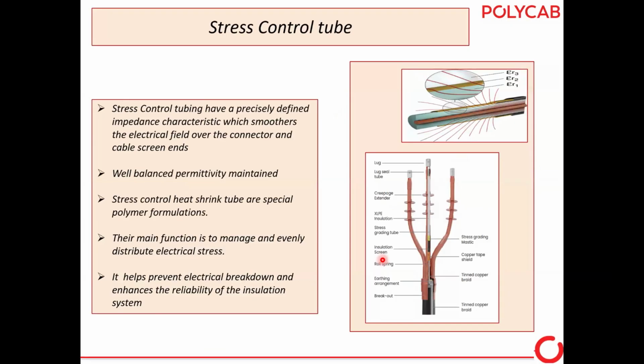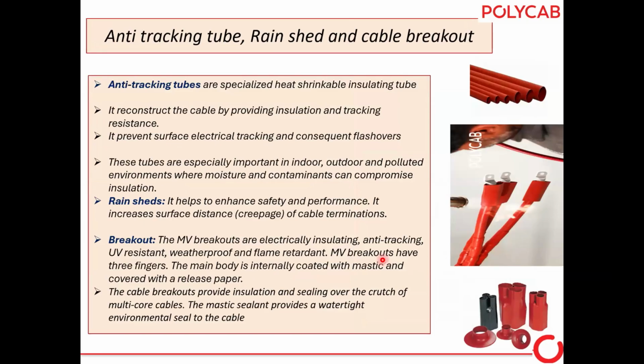Like the stress control tube in the joint, the same function is there in the termination also, because stresses also develop in the termination. Same functions, same application. So I will not go into detail about it here in the termination part. Anti-tracking tubes, rain sheds, and cable breakout: these three are the important parts in the termination. The anti-tracking tube is a specialized heat shrink insulating tube. It reconstructs the cable by providing insulation and tracking resistance. It prevents surface electrical tracking and consequent flashovers also.